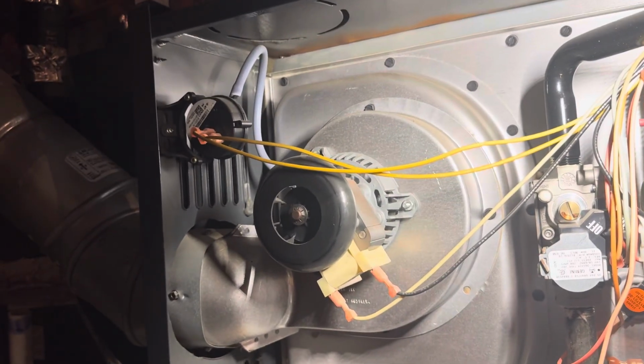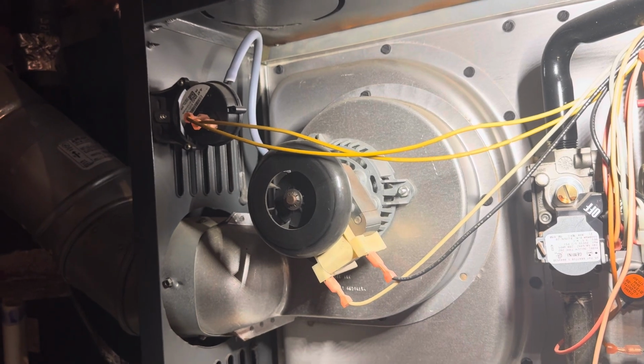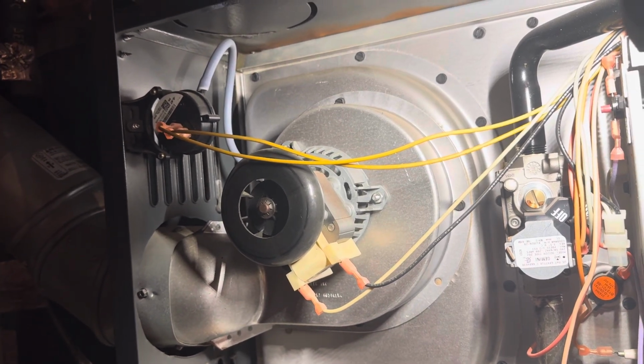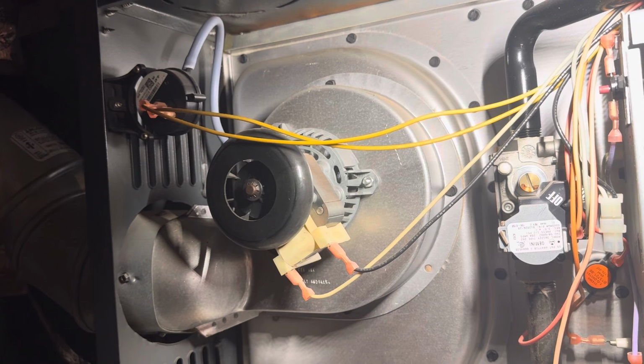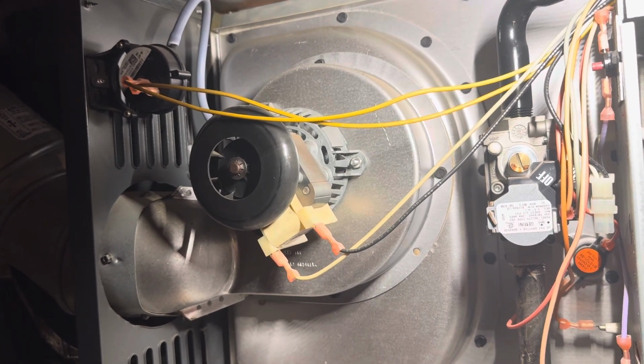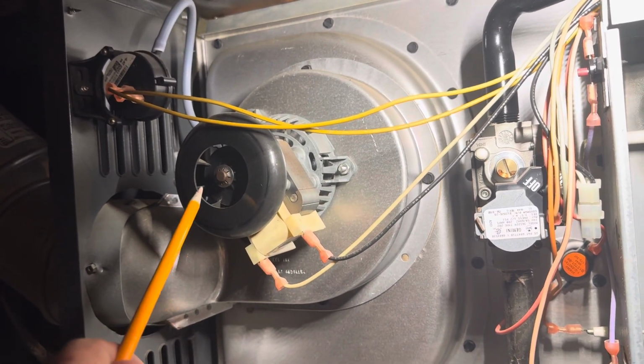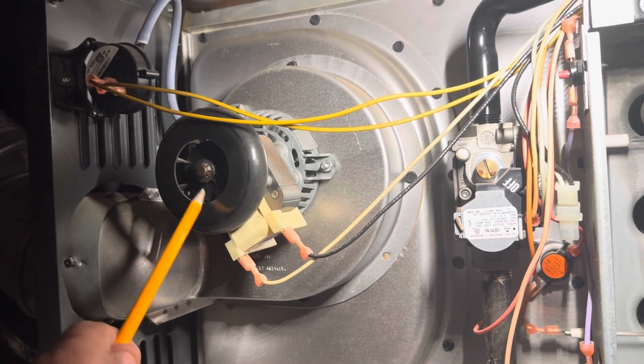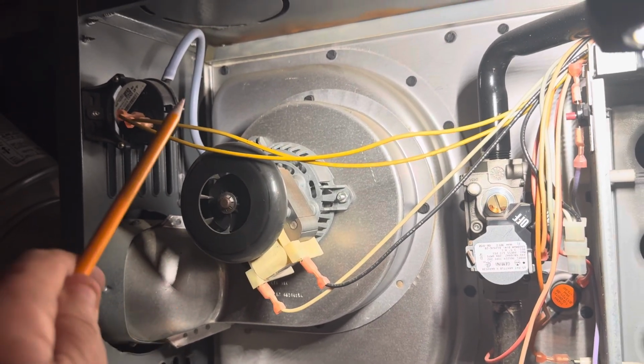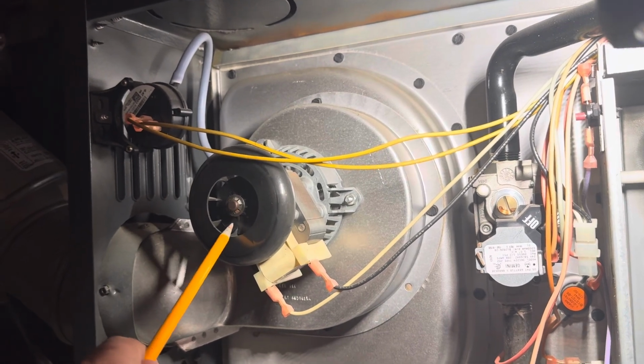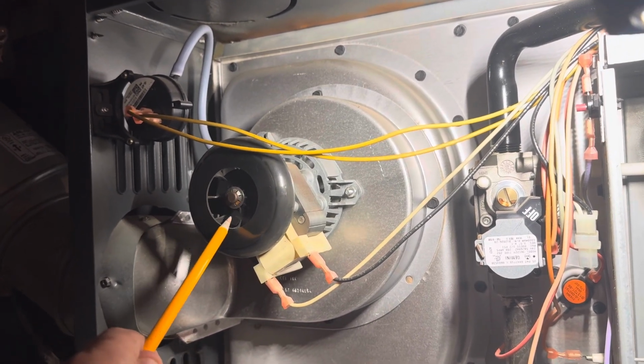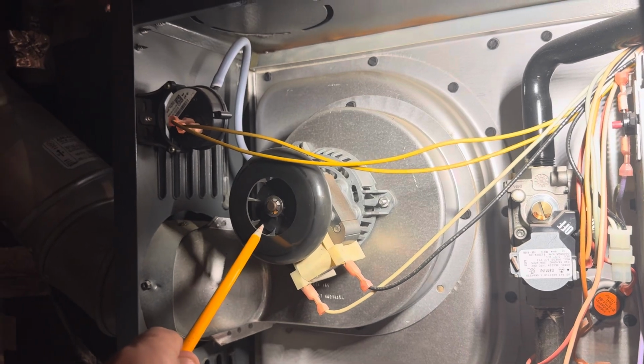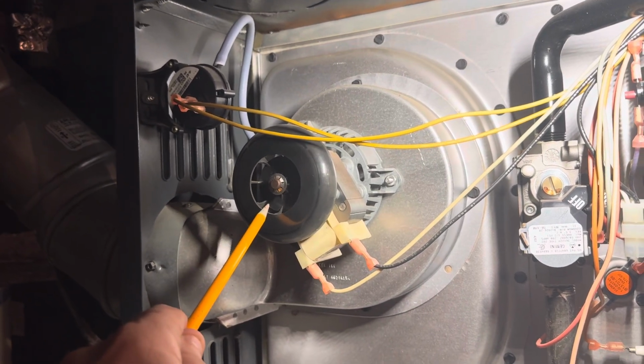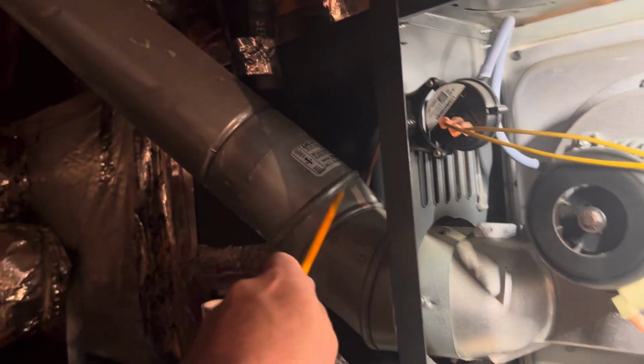So talking about the sequence of operations, again, the thermostat sends a message to the control board to start the heat operation. The control board is going to send a message to this right here, which is the inducer motor. The inducer motor has a really important job to remove and expel the combustion gases and fumes as a result of the burning of gas through the flue pipe and out through the roof in this case.